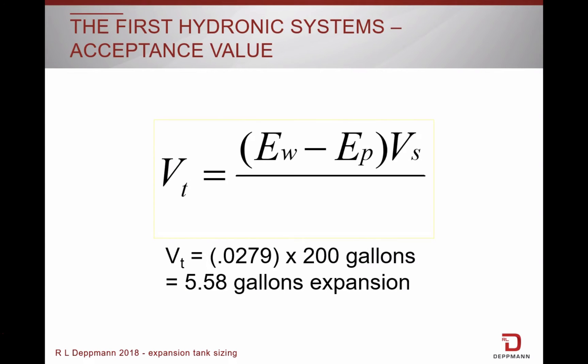Here is an example. If the volume of the water was 200 gallons in the system, and the expansion of the water minus pipe at 180 degrees was 0.0279, the tank in the attic would need to handle 5.58 gallons.